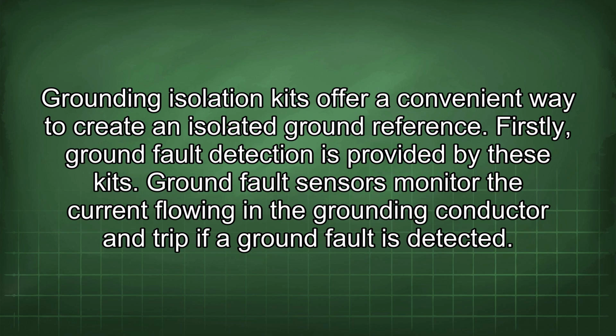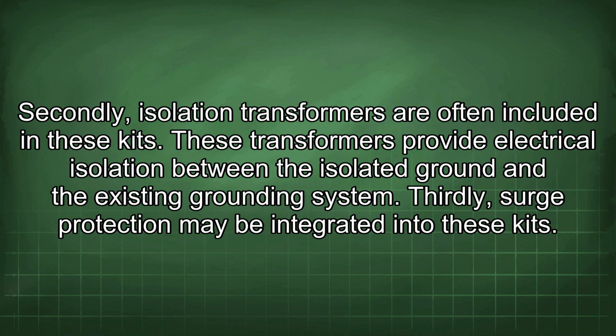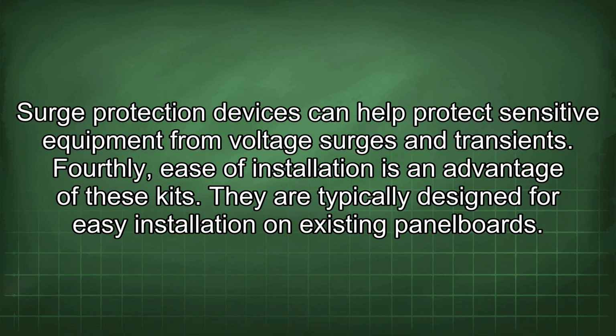Ground fault sensors monitor the current flowing in the grounding conductor and trip if a ground fault is detected. Secondly, isolation transformers are often included in these kits. These transformers provide electrical isolation between the isolated ground and the existing grounding system. Thirdly, surge protection may be integrated into these kits. Surge protection devices can help protect sensitive equipment from voltage surges and transients. Fourthly, ease of installation is an advantage of these kits. They are typically designed for easy installation on existing panel boards.